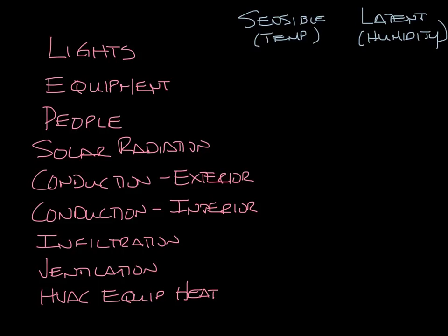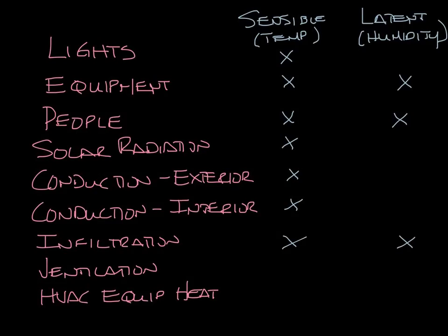The lights don't raise the water content of the air, so they're just sensible loads. The equipment could do both — like maybe a coffee maker would put humidity into the air. People are both a sensible and latent load. Solar radiation is sensible only. Conduction is also sensible. Infiltration will be sensible and latent. Ventilation will be sensible and latent. And the heat from the HVAC equipment will be just sensible.